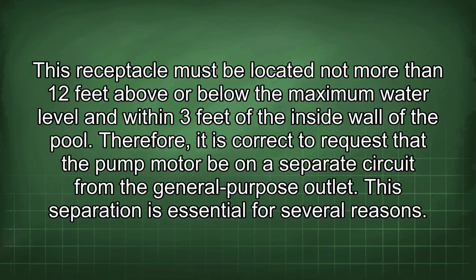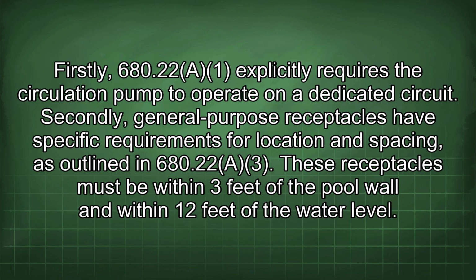This receptacle must be located not more than 12 feet above or below the maximum water level and within 3 feet of the inside wall of the pool. Therefore, it is correct to request that the pump motor be on a separate circuit from the general-purpose outlet. This separation is essential for several reasons. Firstly, 680.22a explicitly requires the circulation pump to operate on a dedicated circuit.